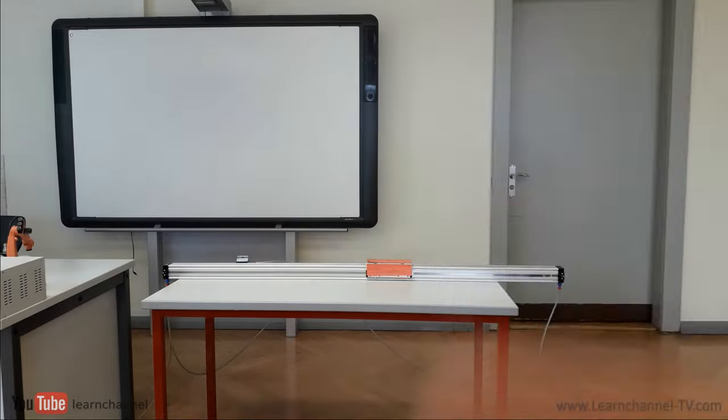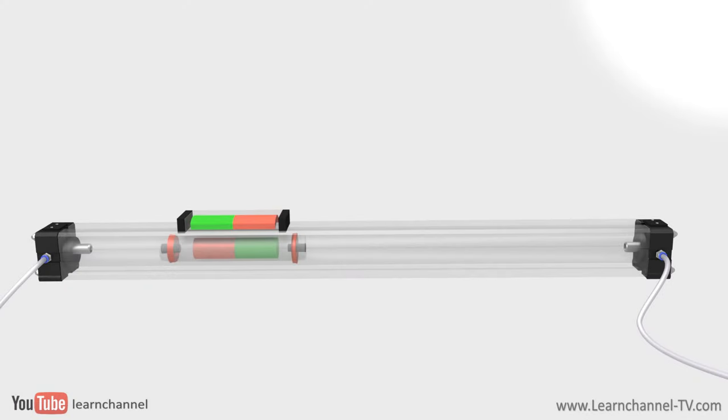Different types of rodless cylinders can be distinguished by the way the piston is connected to the carrier. One principle is the magnetic coupling. Here, the piston and slide are connected together by using permanent magnets. One magnet integrated within the slide, the other one within the piston.